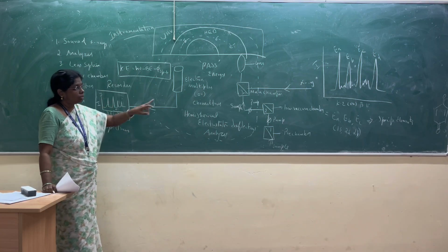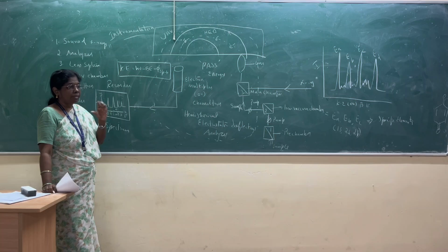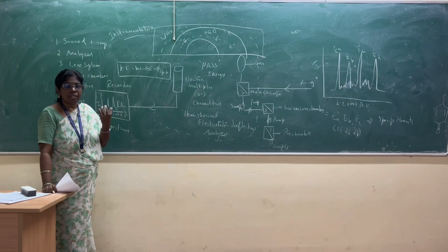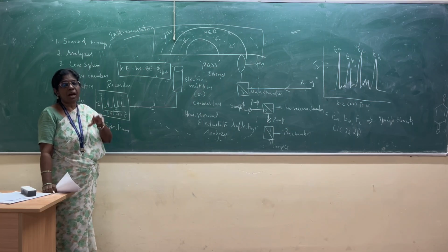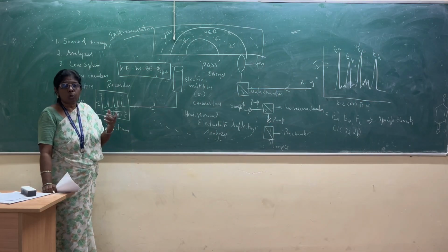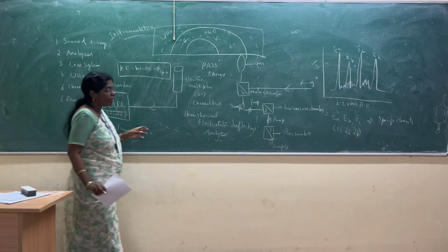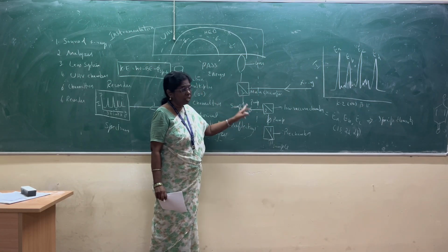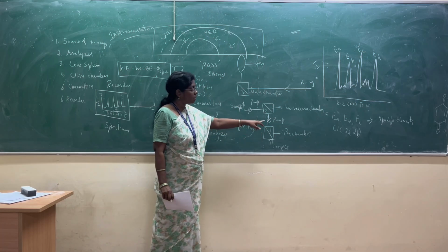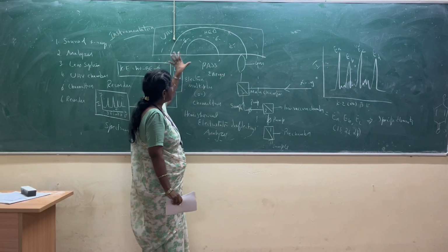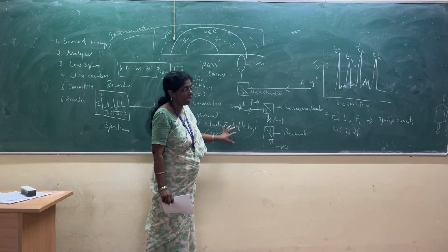How are the X-rays produced? When a 10 milliampere current is applied, the filament gets heated up and electrons are released. They are accelerated and bombarded onto a metallic anode, and the anode is covered with a water jacket for cooling. And another one is the block diagram. Three chambers are there: chamber 1, chamber 2, chamber 3. The sample is introduced into the pre-chamber, then pumped into the low vacuum chamber, then pumped into the main chamber. The main chamber is the UHV chamber, ultra high vacuum.